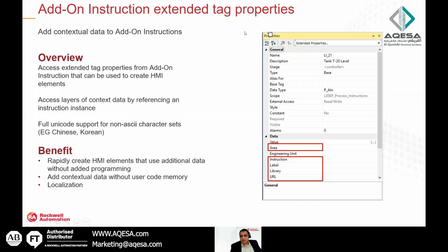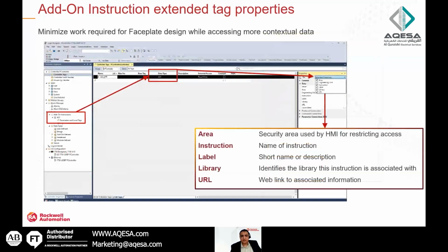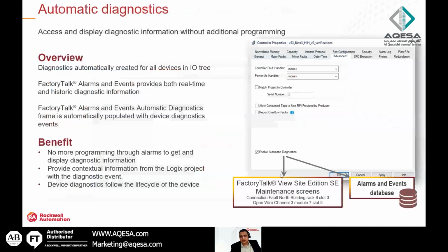Add-on instruction extended tag properties - if you know what extended tag properties are, inside the DCS CPU you can put information about the tag, the area of this tag, the instruction, the label, the library, where it is. Even the URL, you can put the URL. All the information is inside the process instruction CPU, so you save a lot of time for the programming inside the SCADA or the HMI part. So when you create a tag inside the HMI, you will have all the information already extended inside the Logix CPU or the Plant PAx CPU.